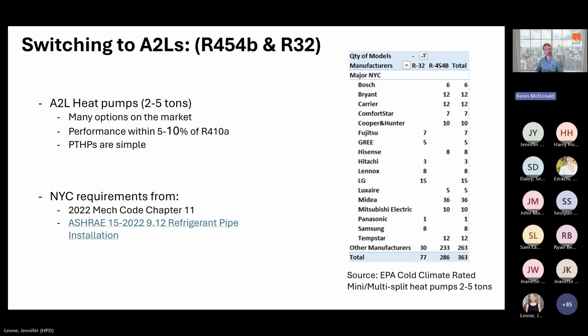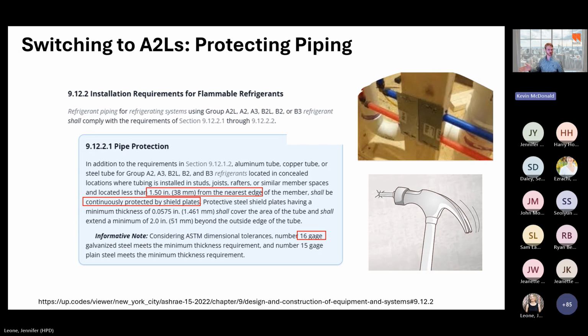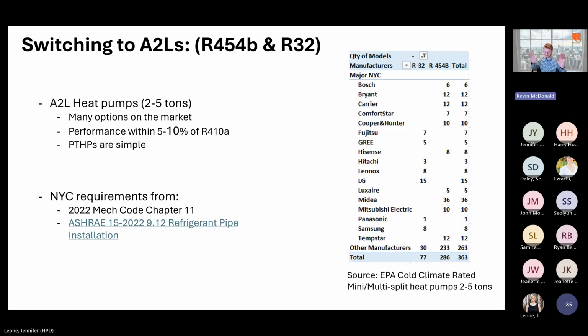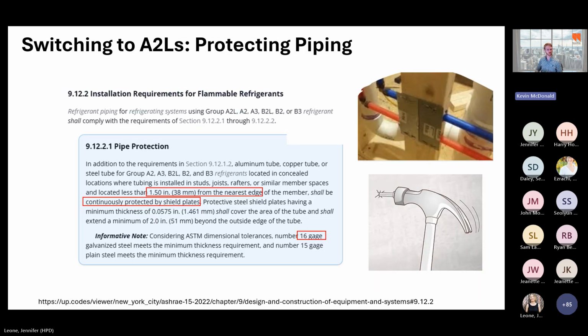The A2L code requirements generally come from our current mechanical code, ASHRAE 15. I want to highlight that there are IMC 2022, 2024 A2L requirements, but that's not part of our jurisdiction. So we're focusing just in the ASHRAE 15 bucket.